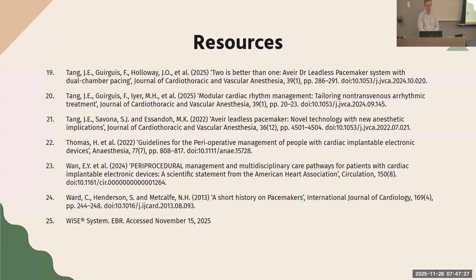The first being that you should always have pads on when you disable or change the mode of a pacemaker. The second, or I guess one of them, being that ICDs occasionally have thresholds that are too high to initiate anti-tachyarrhythmia therapy. And so they won't defibrillate or they won't initiate ATP. And so the patient will be in this kind of weird in-between rhythm where they're not being shocked, but they're also not at an appropriate rhythm. So that's something to be aware of.